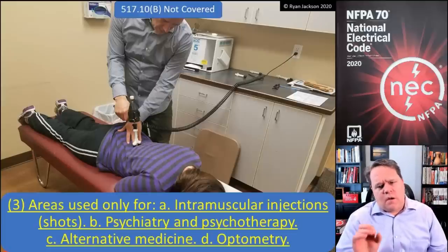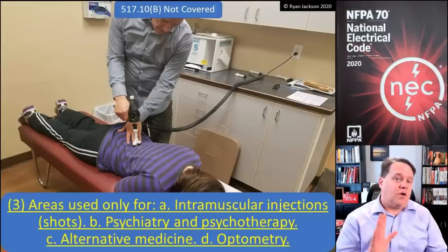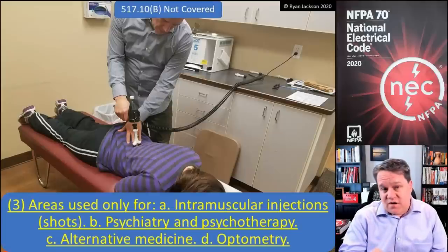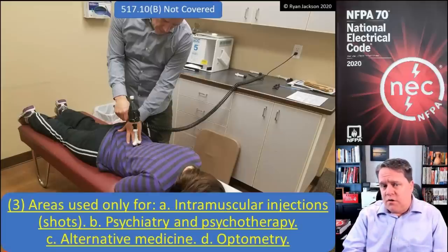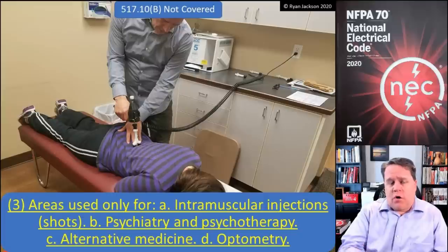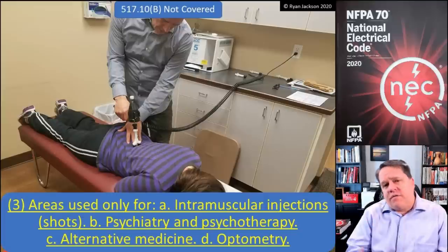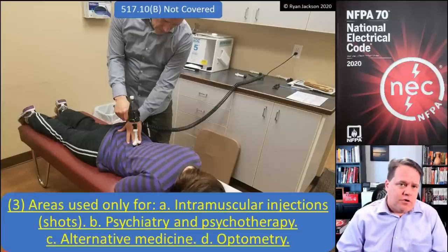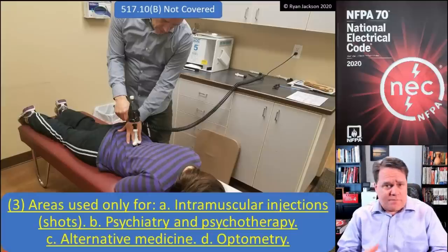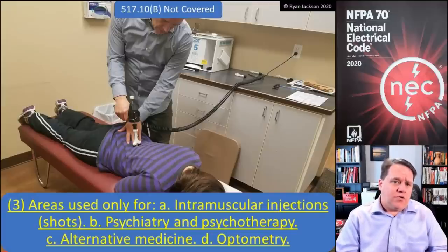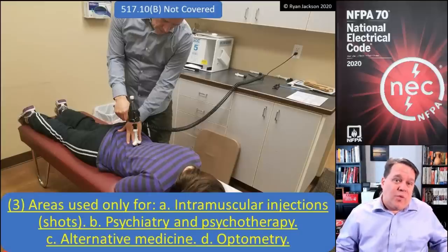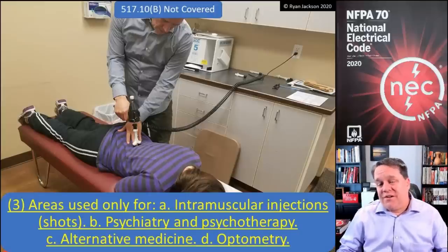We could say the same thing about psychiatry and psychotherapy. Although those are definitely healthcare facilities — the definition of healthcare facility specifically mentions psychiatry — we have the same argument: are you really any more electrically vulnerable at your psychiatrist's office? They are indeed patient care spaces, but the examination and treatment is just you and the doctor sitting in chairs talking. Do we really need to wire that building any differently than an office building? Probably not. So it's a really nice change in the 2020 code.